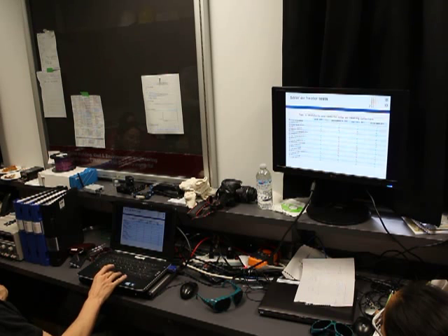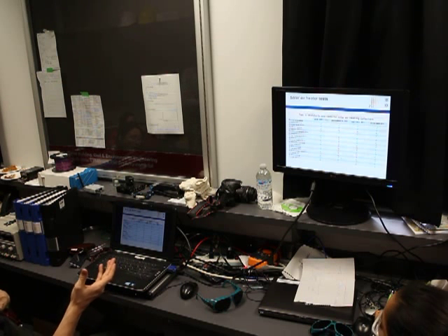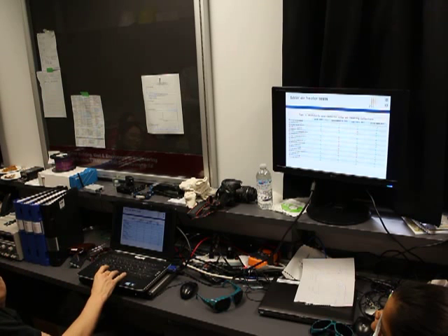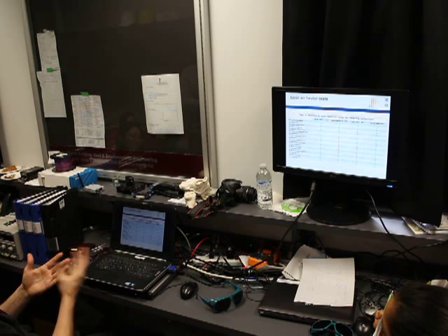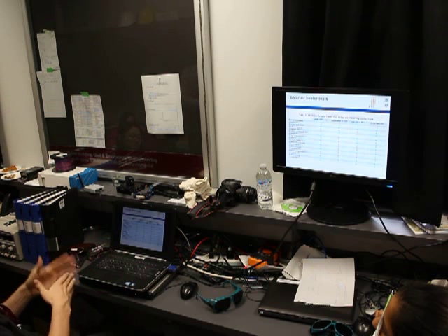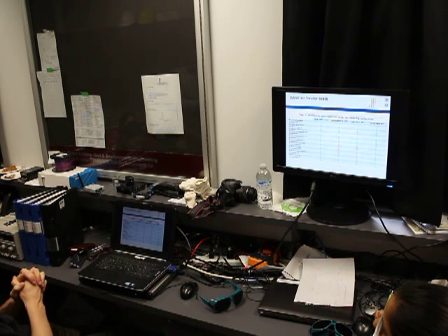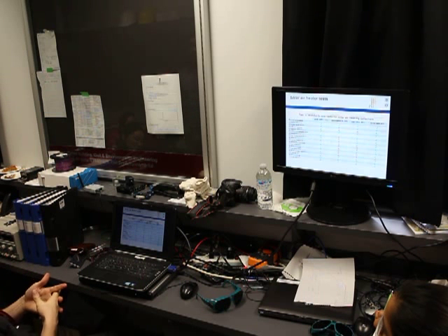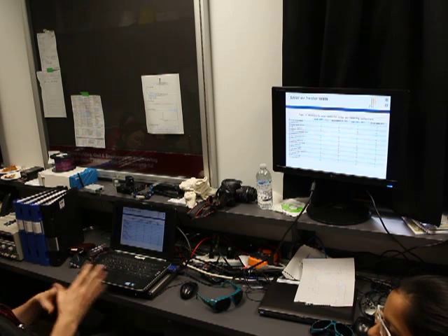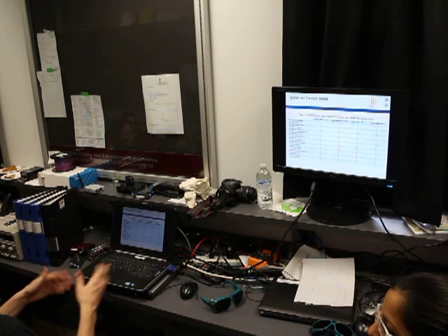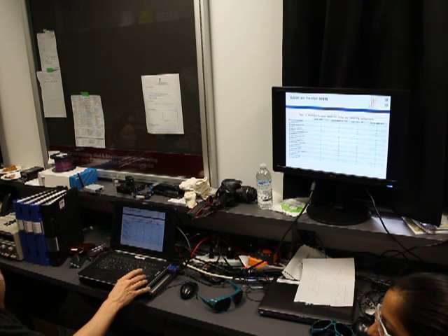What everybody is testing is the leakage of the collector, so how much air goes in or out of the collector, which you don't predict. Then the pressure drop over the collector is also tested by all of the standards, and they all make a final inspection. So, for example, opening the collector and seeing what happened during the tests, just seeing if anything was damaged, something like that.